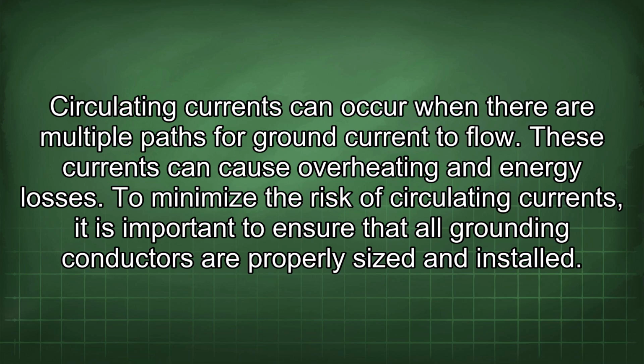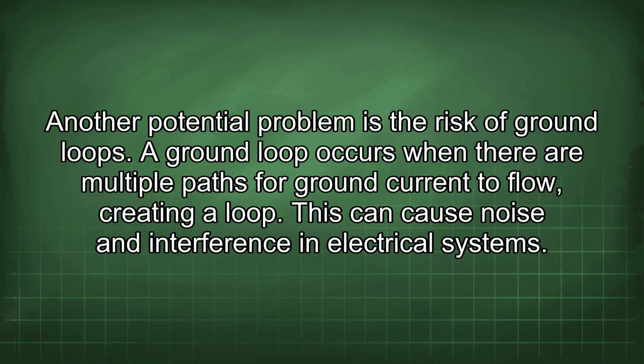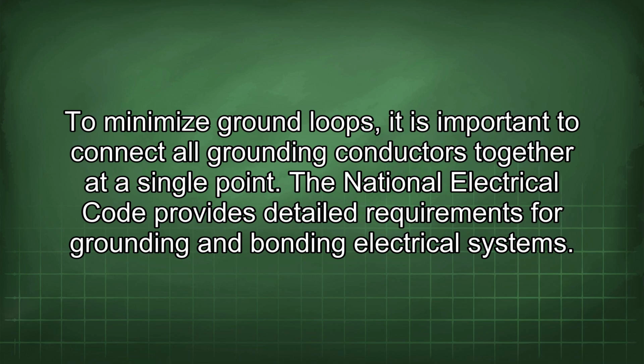To minimize the risk of circulating currents, it is important to ensure that all grounding conductors are properly sized and installed. Another potential problem is the risk of ground loops. A ground loop occurs when there are multiple paths for ground current to flow, creating a loop. This can cause noise and interference in electrical systems. To minimize ground loops, it is important to connect all grounding conductors together at a single point.